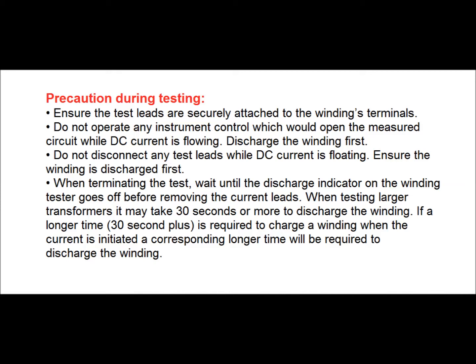If a longer time is required to charge a winding when the current is initiated, a correspondingly longer time will be required to discharge the winding. It must be ensured that after the winding is fully discharged, the connecting leads should be removed for the next testing in the next phase.